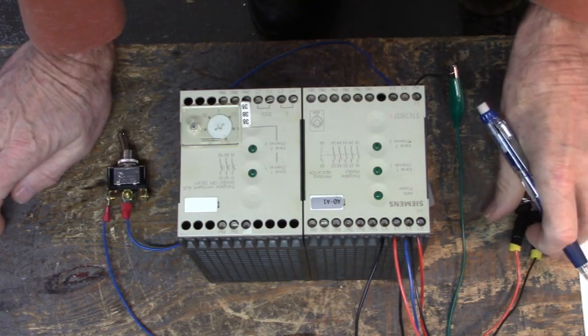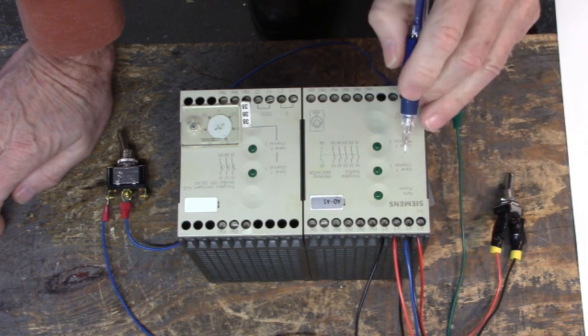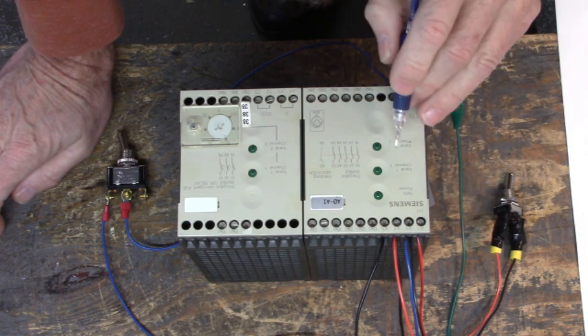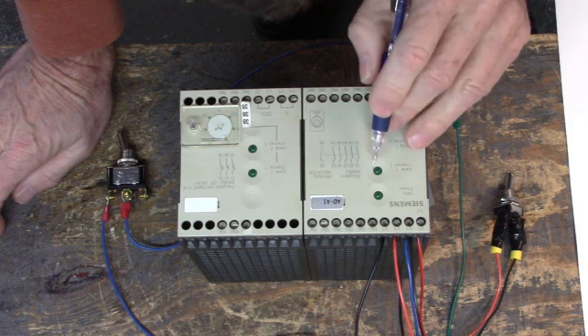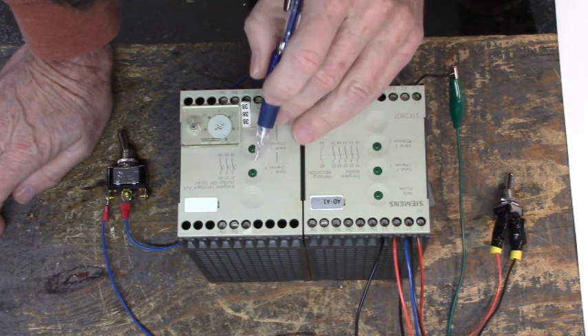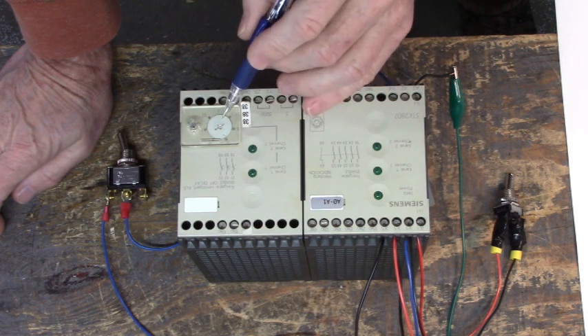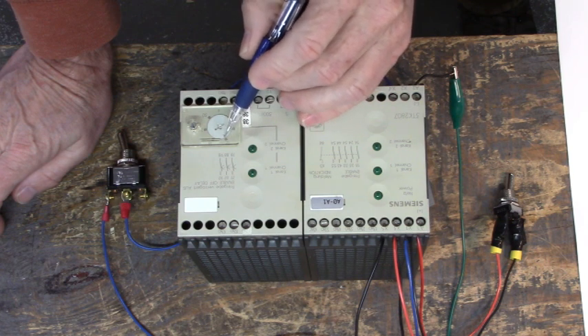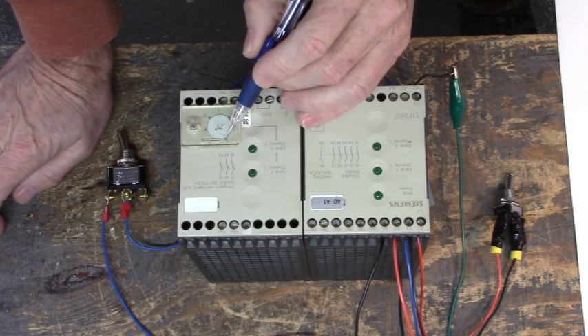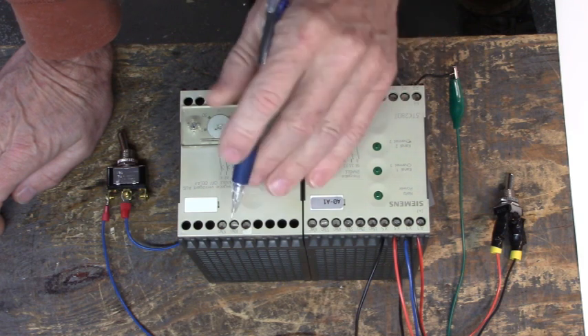The same X1 that this switch goes to. And when I open this switch, these two contactors will open up, the channel 1 and the channel 2 contactors. And these contactors over here, they're on a time delay set by this dial. And right now, it's set to just a hair less than 12 seconds.